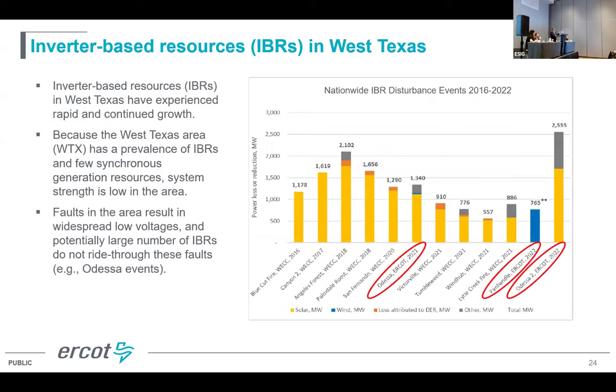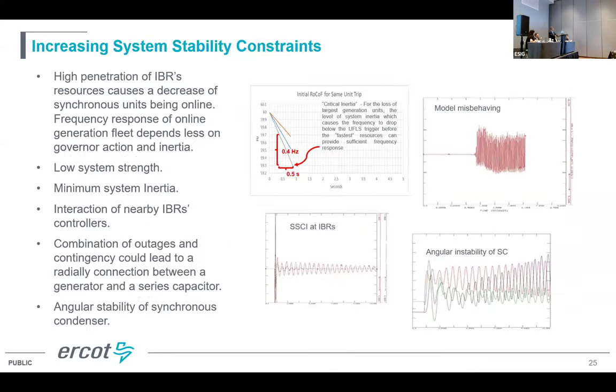Changing topics here, IBRs, I'm going to lay out some of the issues. You've probably heard or seen a lot of those reports, especially the NERC reports. There were three events within ERCOT, two in Odessa and one in the Panhandle. Those events, normal faults in the system, tripped several thousand megawatts of renewable resources, which is not supposed to happen because they should be able to ride through these events, but they didn't. Following that, we've been spending a lot of time looking at IBR issues.